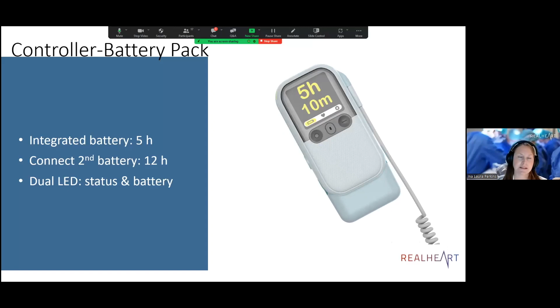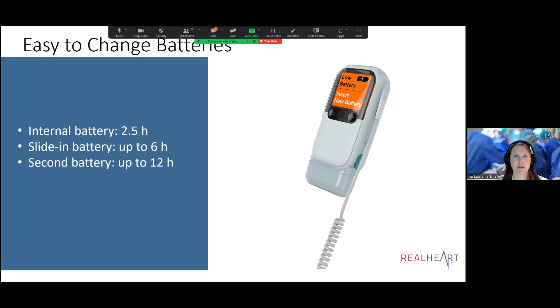And it should be easy to change these. So we're working on this slide in, slide out battery. When you pull this out, you still have an internal battery that lasts up to 2.5 hours. So it's not unsafe to disconnect. But then when you put this in, when it's closed, you have about up to 6 hours, 5-6 hours. And then if you connect that second battery I just mentioned, then you would have up to 12.